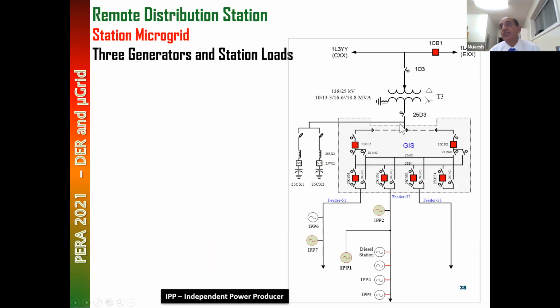These are the details of the station feeders. There are 3 feeders, 51, 52, 53. This is the longest feeder, 52, which has IPP1, the largest 10 MVA generator. This is the second largest and third largest. The rest are very small. There are 7 IPPs. Now some of us decided that we have all the infrastructure and the ability to supply this load. Why not operate as a microgrid? We said we will operate these three generators to supply the load depending on the water in the river. All three of them can supply this station load.